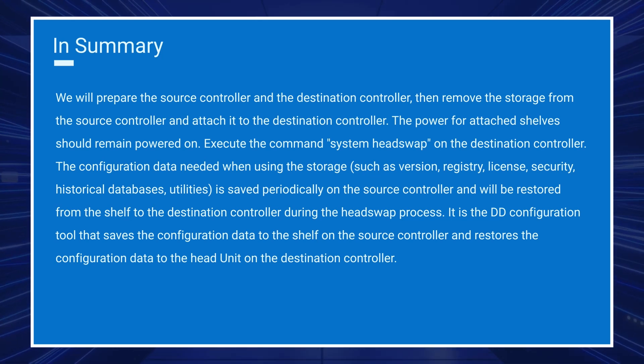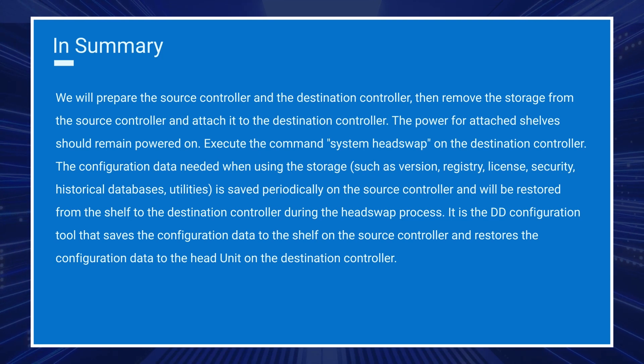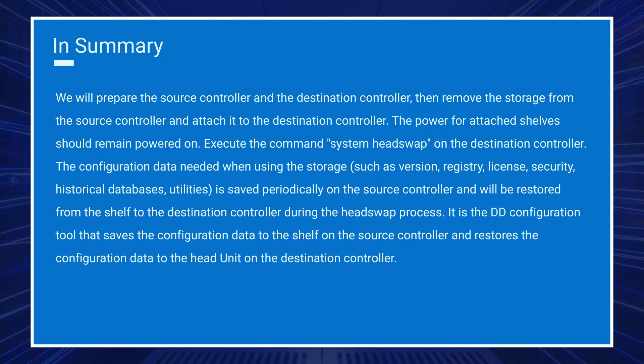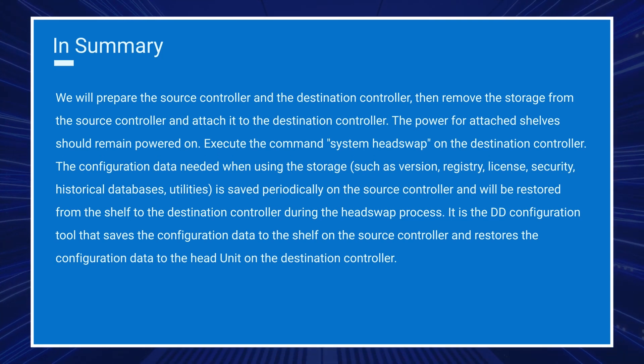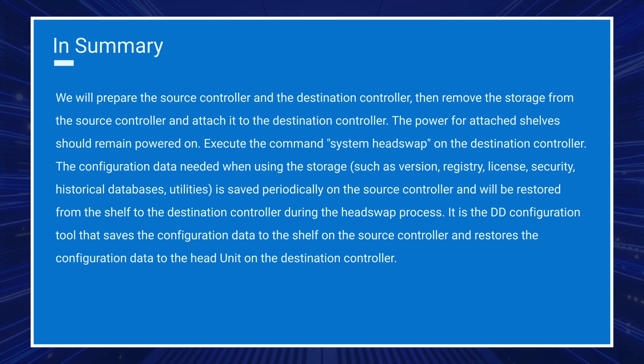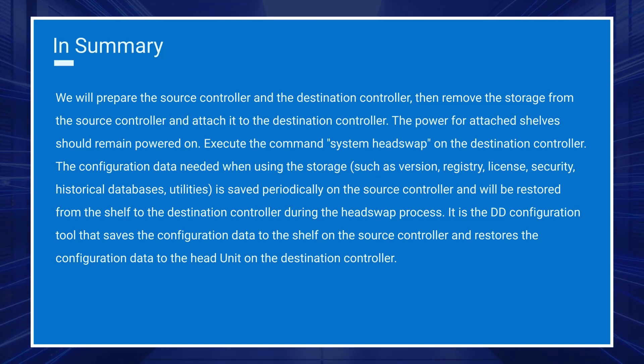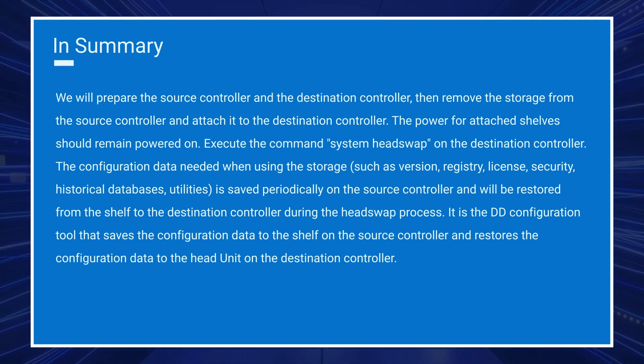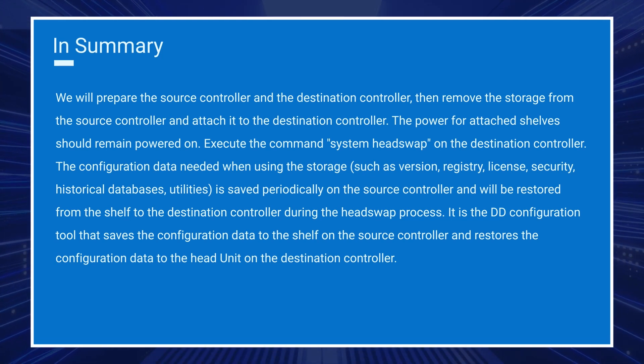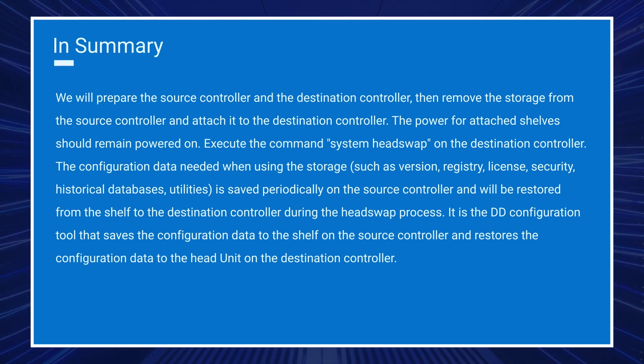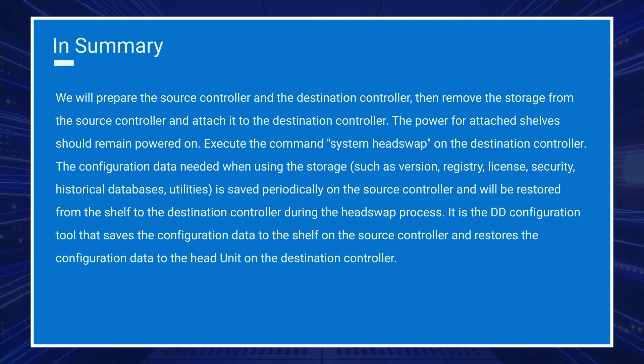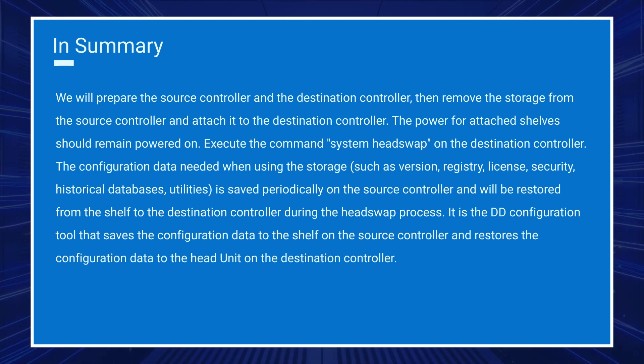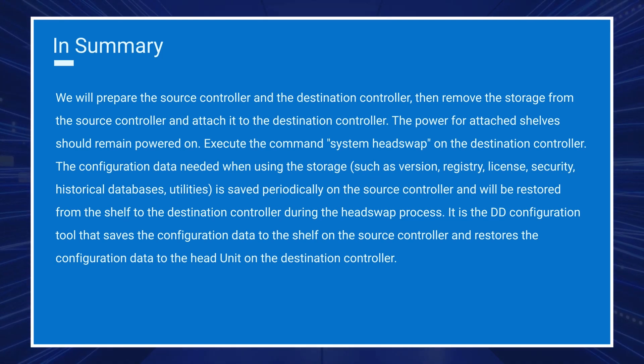The configuration data needed when using the storage such as version, registry, license, security, historical databases, utilities, is saved periodically on the source controller and will be restored from the shelf to the destination controller during the head swap process.